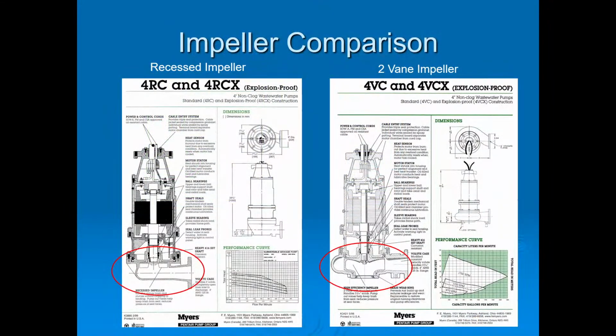So here is a vortex impeller on the left, a 2-vane impeller on the right. I'll show you videos here in a second. You'll see the vortex generates something like a tornado inside the volute. I'm from Kansas, so I can say tornado. It has a tornado inside the volute, but the solids never go through the impeller.